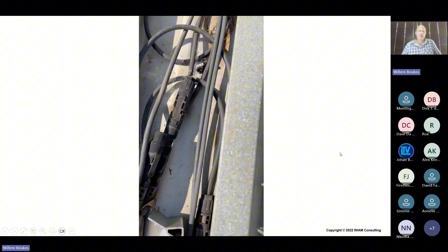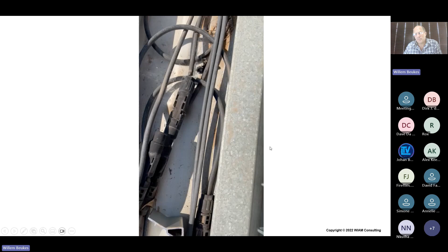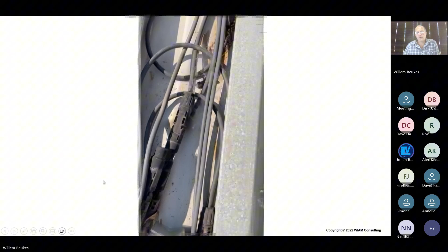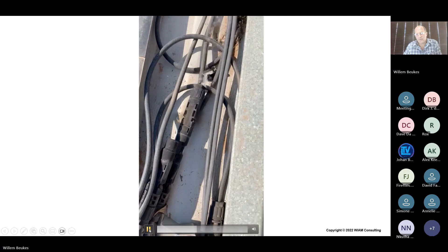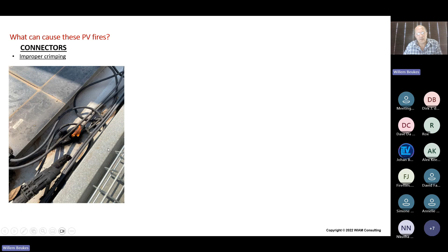When we look at some portions of the electrical system on a PV installation, we have a big issue with PV connectors, where you have arcing happening on a PV connector. Here we see arcing happening on an MC4 connector, and it's actually melting away the whole MC4 connector while the arc happens on a DC level inside that connector. Now, what is the cause of most of these fires? In this case, there was improper crimping of the MC4 connector, which caused a separation gap between the anode and the cathode side of that connector.